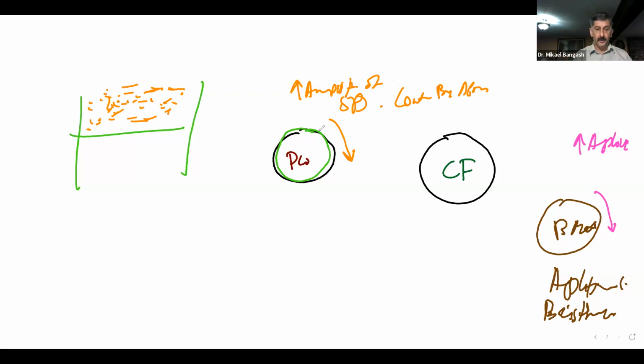So the way to get rid of this is, you can just turn this knob here anti-clockwise, because that's going to reduce the amplification of the Doppler signal, but also reduce the noise.